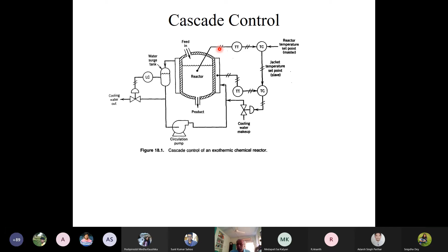To ensure that, we have to configure this control as a cascade control configuration. So we have a slave loop over here which basically maintains the jacket temperature. We measure the jacket temperature, and we have a temperature controller which manipulates the cooling water control valve. And the master controller, which is the reactor temperature controller, takes the input as the reactor temperature measurement, and the output is the set point of the slave controller, that means the jacket temperature controller. Okay, so this is basically a cascade control configuration strategy.